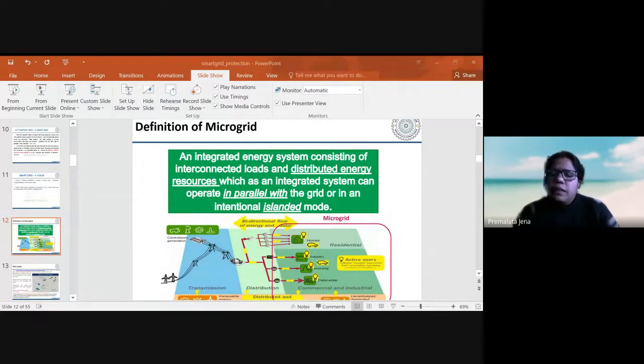So for AC microgrid, we have different types based on voltage level - medium voltage AC microgrid, low voltage AC microgrid, high voltage AC microgrid. You can start from 66 kV onwards, 33 kV onwards, 11 kV onwards, or 440 volt onwards. When we land at 440 volt, we call it low voltage AC microgrid; at 11 kV or 33 kV we call it, or 66 kV we call it medium voltage AC microgrid.